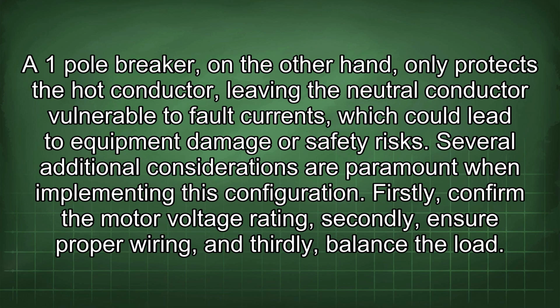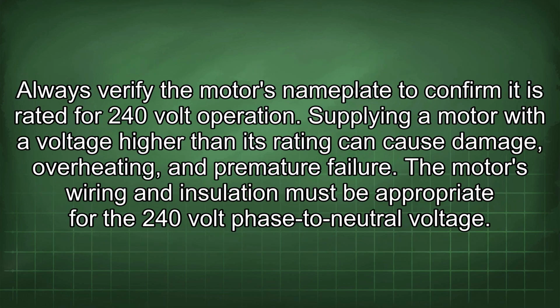Several additional considerations are paramount when implementing this configuration. Firstly, confirm the motor voltage rating. Secondly, ensure proper wiring. And thirdly, balance the load. Always verify the motor's nameplate to confirm it is rated for 240-volt operation. Supplying a motor with a voltage higher than its rating can cause damage, overheating, and premature failure.